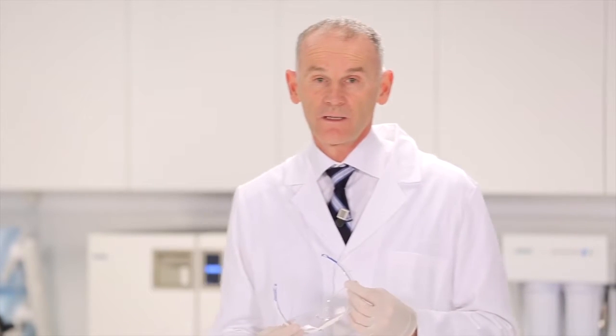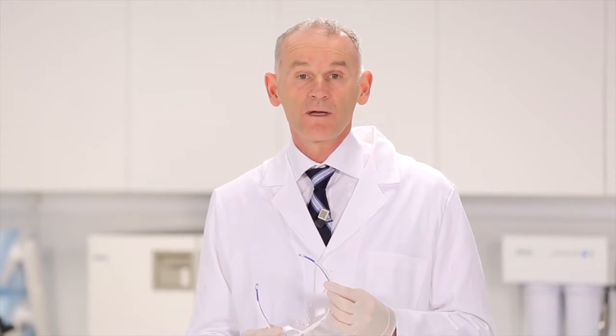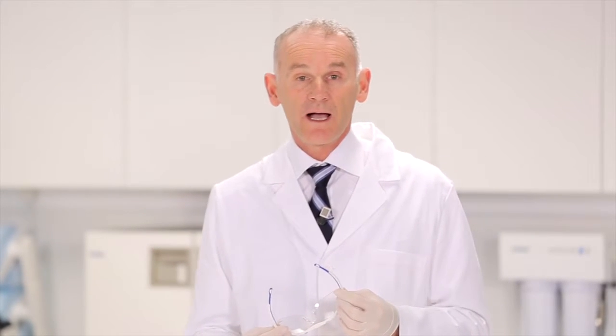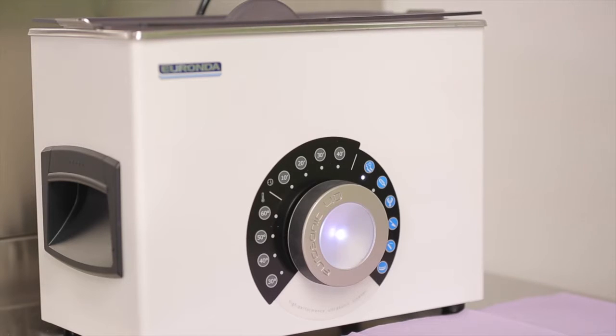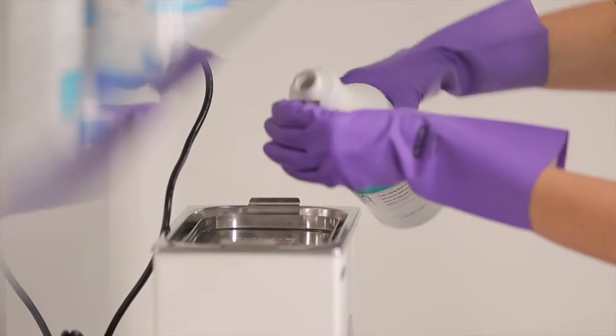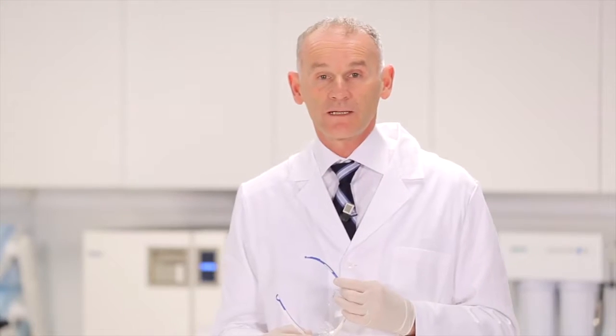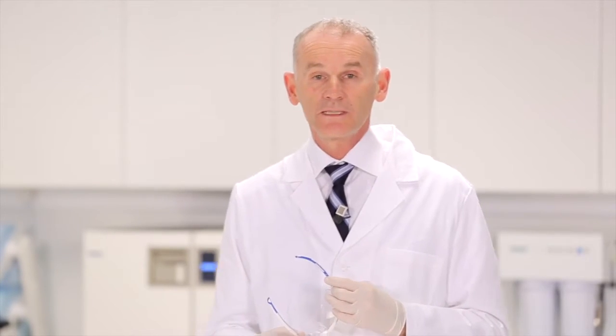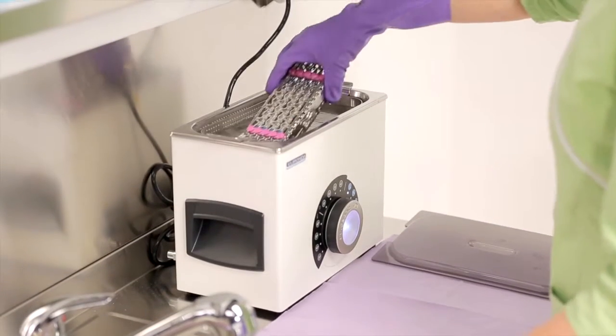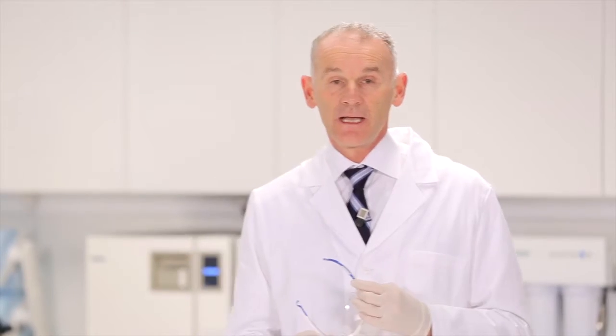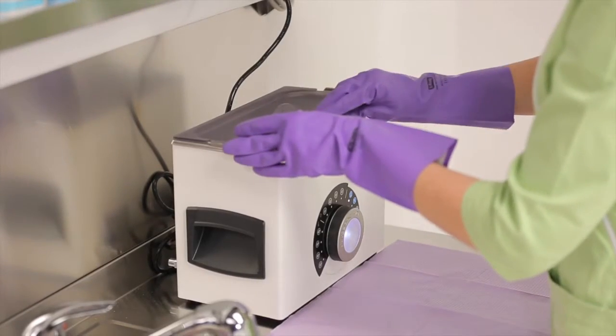The cleaning stage enables organic residues to be removed. It can be carried out manually or mechanically using a thermo-disinfector or an ultrasonic tank. The ultrasonic tank will be prepared with a specific product, observing the dilution percentages and the immersion time. The combined action of the disinfectant detergent product with the ultrasonic tank waves will enable the liquid to also disinfect the areas that cannot be reached by the instrument. The ultrasonic tank will be used for the complete immersion of the instruments.